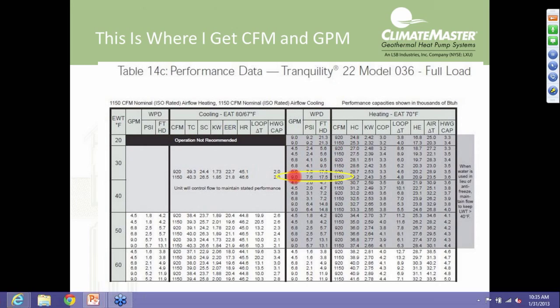Next, I look at my CFM. For each water flow, I have 2 airflow specifications, either 920 or 1150 in the case of this 036. So, I pick one of those. I drive my airflow to 1150 CFM in the manual mode, and the blower is going to go to that mode. Next, I've got my water flow now.